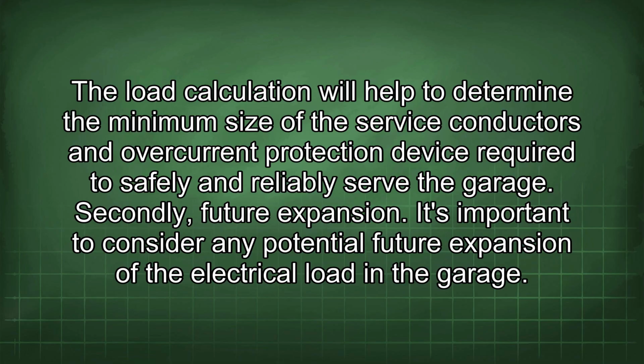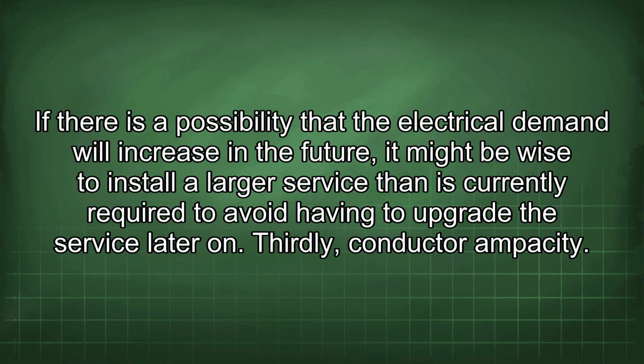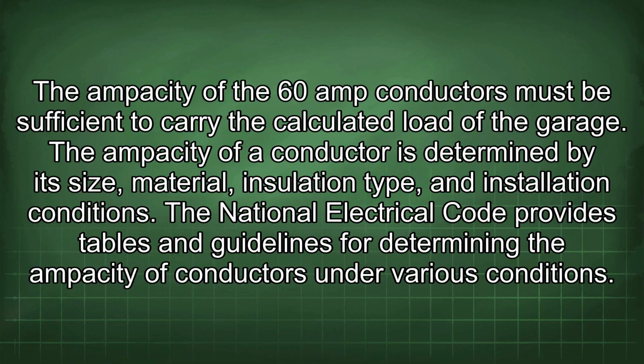Secondly, future expansion. It's important to consider any potential future expansion of the electrical load in the garage. If there is a possibility that the electrical demand will increase in the future, it might be wise to install a larger service than is currently required to avoid having to upgrade the service later on. Thirdly, conductor ampacity. The ampacity of the 60 amp conductors must be sufficient to carry the calculated load of the garage. The ampacity of a conductor is determined by its size, material, insulation type, and installation conditions. The National Electrical Code provides tables and guidelines for determining the ampacity of conductors under various conditions.